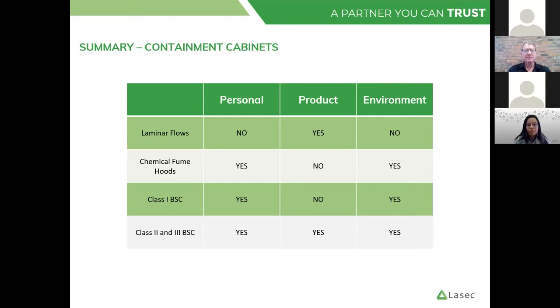There is a distinctive difference in that laminar flow cabinets generally do not have that front air grill. So if you are sitting in front of a cabinet that doesn't have that air grill where the two air flows meet, then you're not sitting in front of a BSC — you're probably sitting in front of a laminar flow and you have no personal protection. So it is very important that you make sure those two don't get confused.